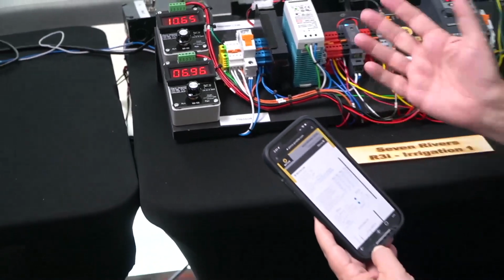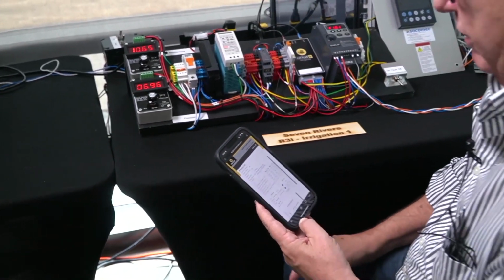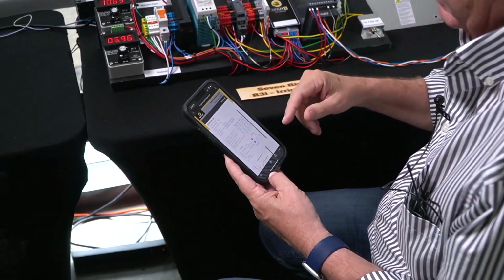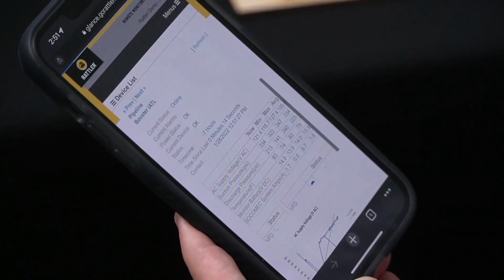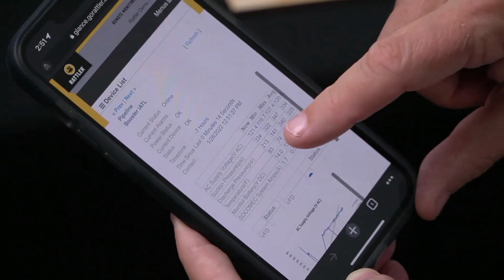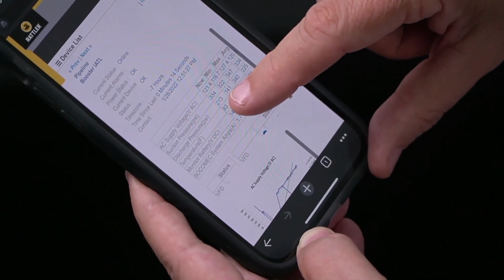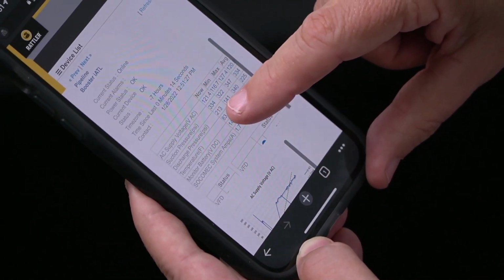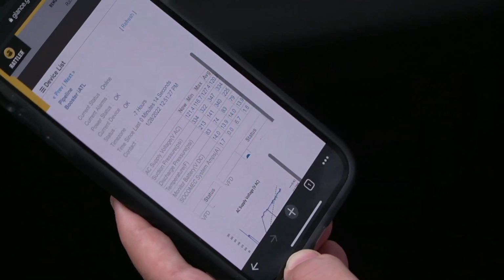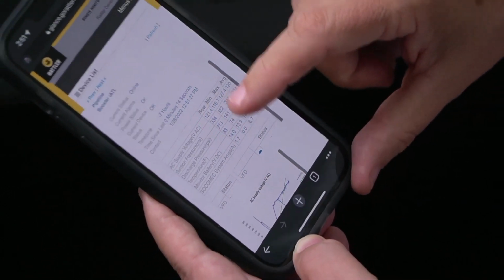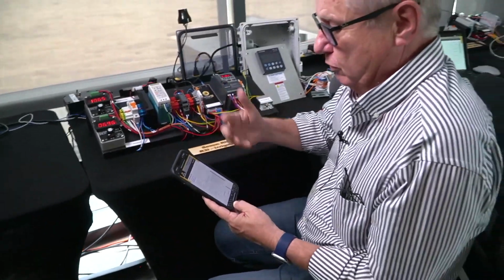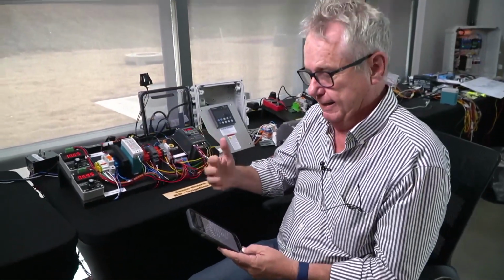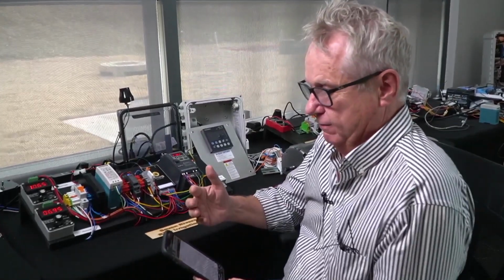Give it a couple of seconds to load up into the cloud, and I can do a reload and see what the current values are. You can see that the discharge pressure is now at 213 psi from 300 and some that it was before. And you can set thresholds and alarms on all of these values. So this is how you can tell when the motor's on and it's not running correctly.